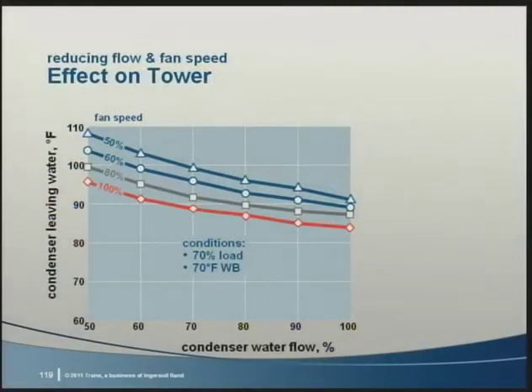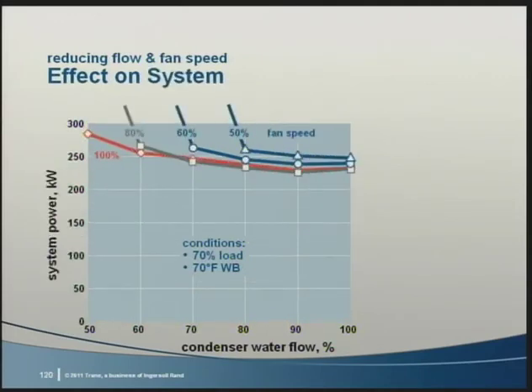Since slowing tower fan speed reduces airflow and heat rejection capability, the tower entering water temperature rises as shown on this chart. Since both water flow and airflow decline, the slope of the curves is steeper than before. So, let's look at all of these flow rates and tower fan speeds and see how the system kW compares. When we look at all the possible operating points, we see that the system kW is at its minimum when the fans and pumps are at about 80 to 90% of their speed. Reducing water flow rate further ends up using more energy in all cases.